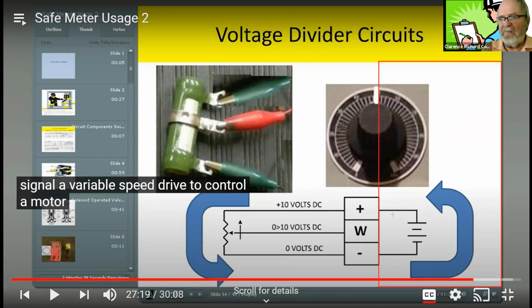So we were talking before, high pressure seeks low pressure. And so this is the return side of our power supply. So we've got 10 volts here, and this is our load. Just think of that resistor as a load. This thing in the middle, think of nothing more than maybe your voltmeter test lead. This is the same signal that's going to go into your variable frequency drive, and it's going to sense it as 0 to 10 volts depending on where you put this. So if we move this wiper up clockwise, in this direction here, we're going to start getting closer and closer to 10 volts.